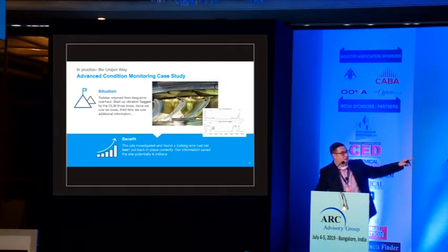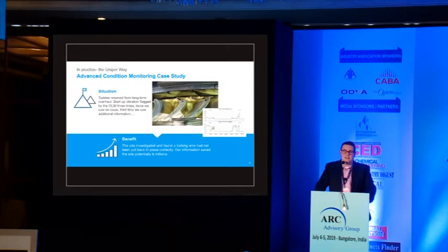However, what we'd also picked up was not just high vibration but also a high temperature. Our team were able to diagnose that this was likely a loss of mass on the first stage rotor. By telling the site in an urgent manner, they were able to take it offline and investigate, and they found they hadn't put a locking wire back in place, which had caused the blades to shear, which could have caused catastrophic damage to the entire turbine, saving millions of pounds.